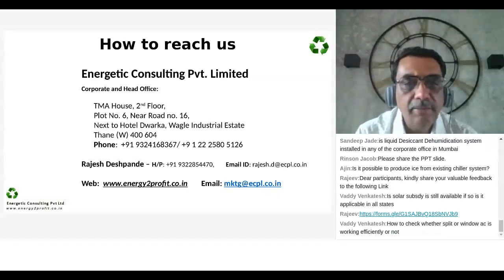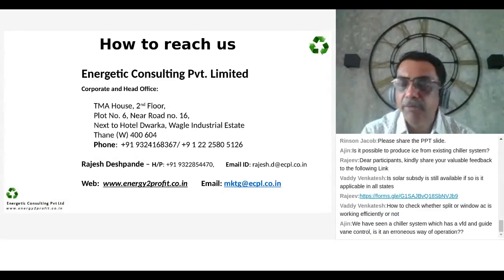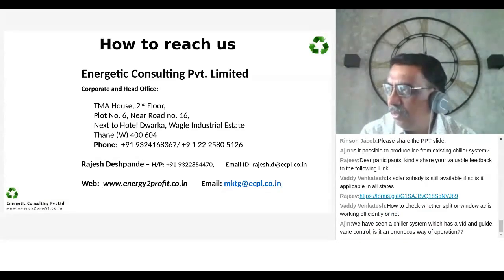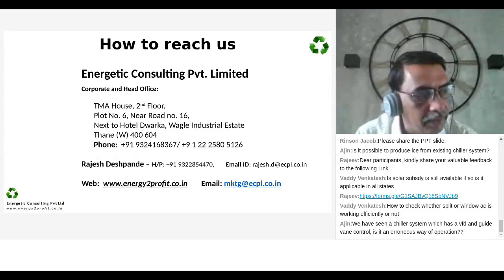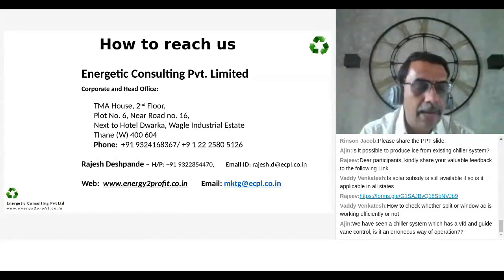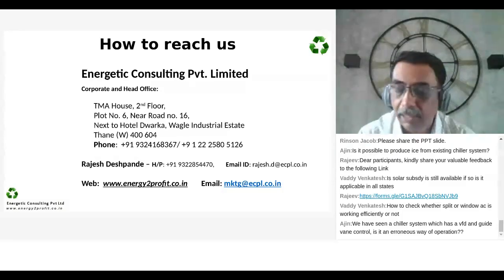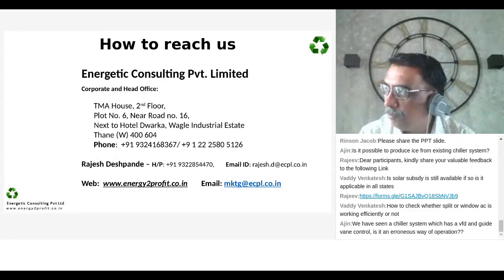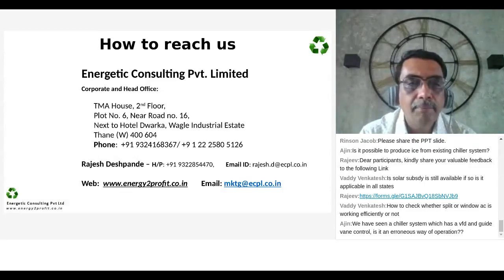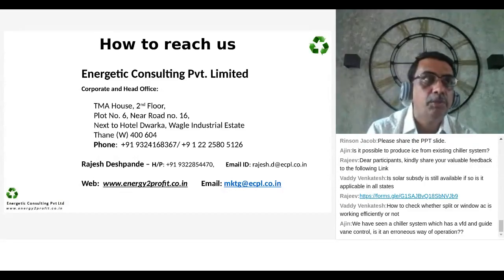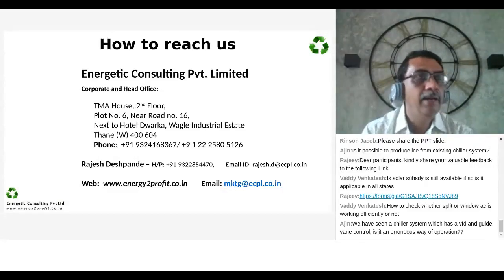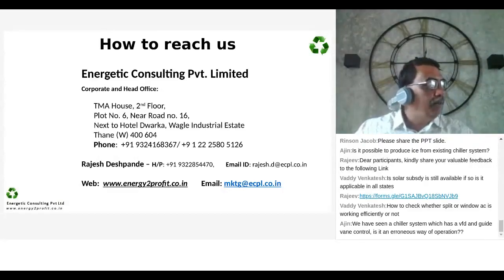How to check whether a split or window AC is working efficiently or not? Whenever you get your AMC done, check your standing pressure and the operating pressures, condenser and evaporator, of the refrigerant. That is the simplest and most practical way of checking. Other checks: what is the grill temperature you are getting in the window or split AC. It's a very good indicator. If you are getting between 5 to 7 degree grill temperature, your AC is probably working properly.